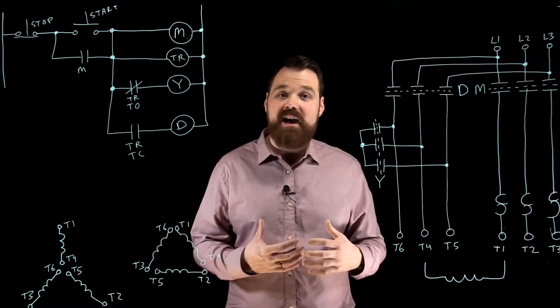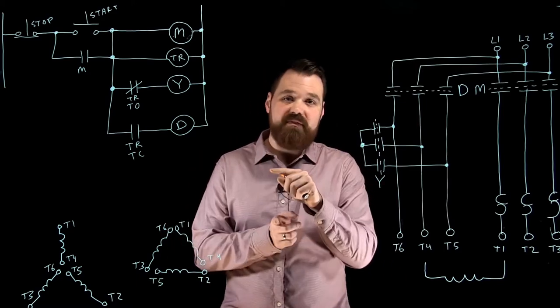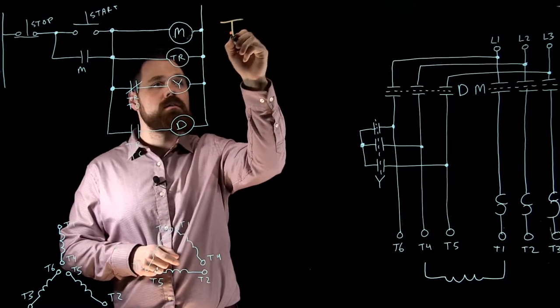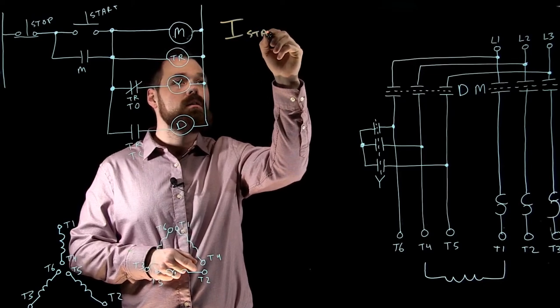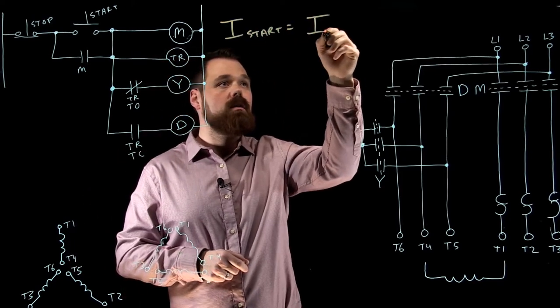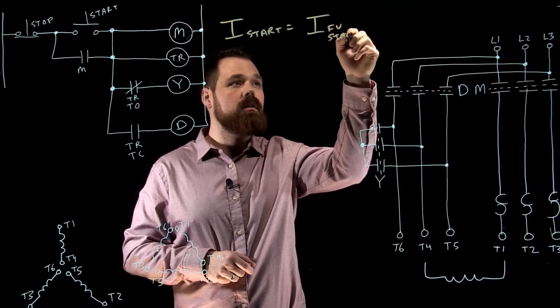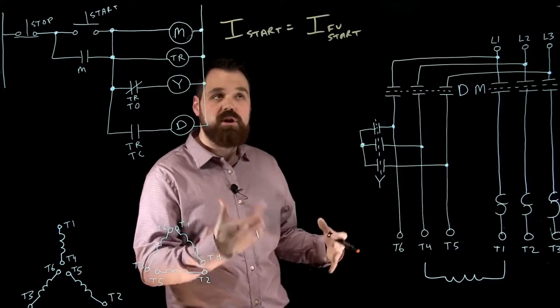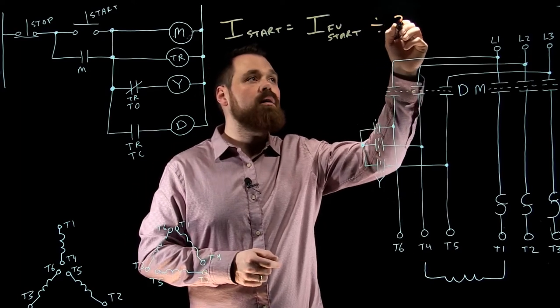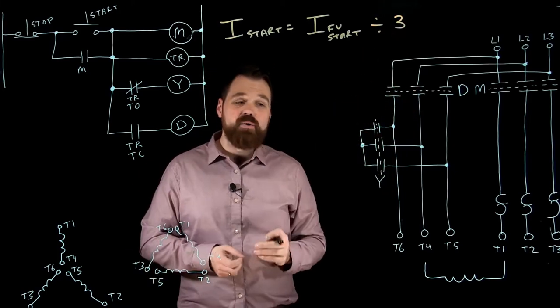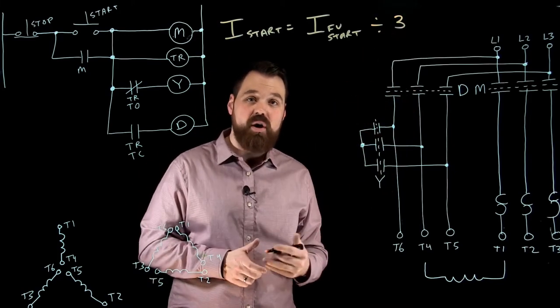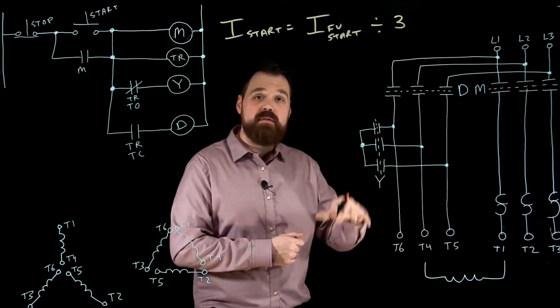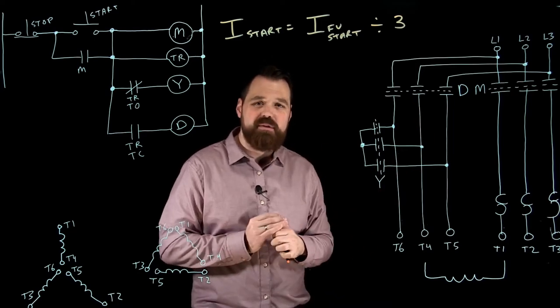The effect this has, because we're reducing the phase voltage, we're not changing the phase impedance. What we see is our current at start is going to be our full voltage start current, which would be if we were to just start this motor in delta, what would our inrush current be, divided by 3. So we actually only see one-third of the starting current, so we only see 33% or one-third of the actual starting current if we were to start it in delta, so we see that huge drop in inrush current, which is great.